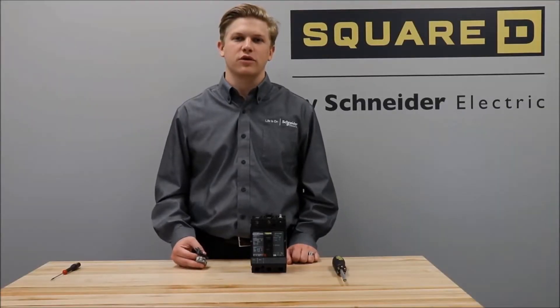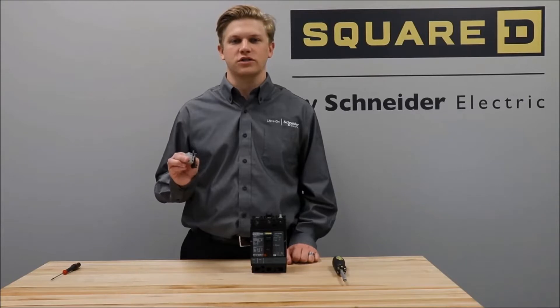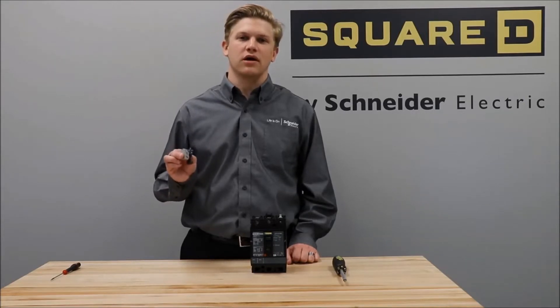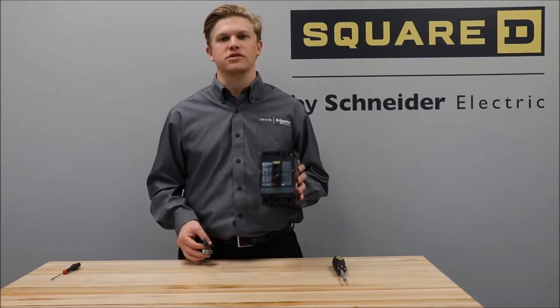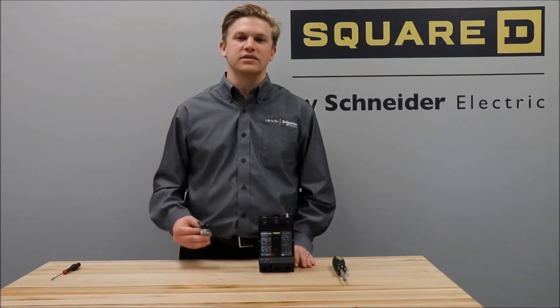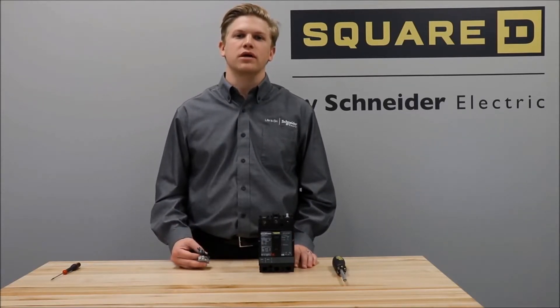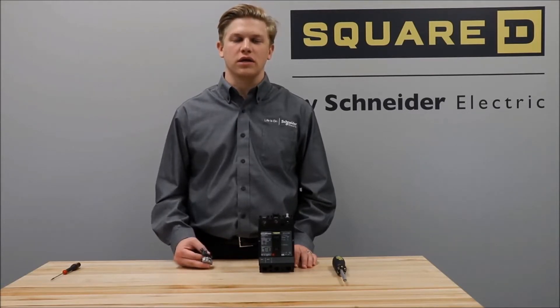In this video, we'll be showing you how to install the S29450 AUX switch with the S29451 SDE actuator into a PowerPact H or J frame circuit breaker. The breaker must be either thermomagnetic or have a standard micrologic trip unit, as the advanced micrologic trip units will come with an SDE already installed into the breaker.